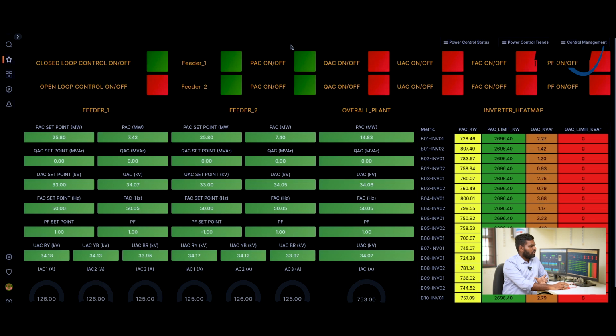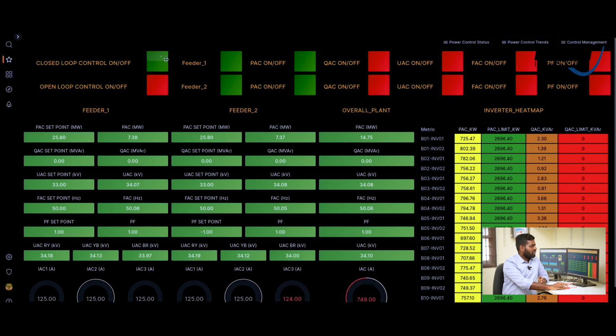This is the heart screen of our PPC. In one screen we can check all control data points and which loops are on and off, which mode is on and off. So the operators can check this on one screen. We are providing a solution of 2 modes of operation. One is open loop control mode and the other is closed loop control mode. If a mode is on, it is indicated in green color. Red color means it's off condition, and also which feeder is on and off. So we can check here which mode is off. There are 2 modes of operation.